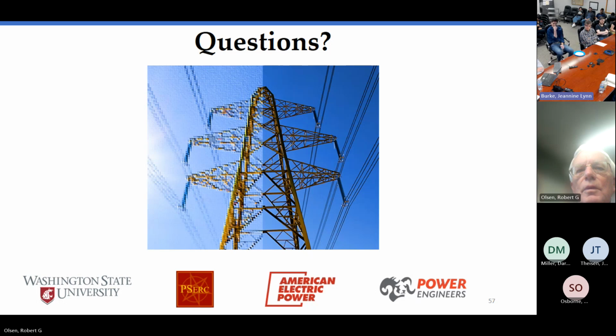Generally speaking, you're well below the critical flashover voltage. Even when, for example, you have a surge, you energize a transmission line for the first time. You just built a brand new transmission line, and you want to make sure, hopefully you've designed it so, that when the voltage doubles at the end, because at an open circuit the voltage doubles on a transmission line, it would be embarrassing if you turned on the transmission line that you built for millions and millions of dollars, and then flashover happened. All right. So normally, even when you have these very high surges, we do not get leaders and streamers and all that sort of thing.